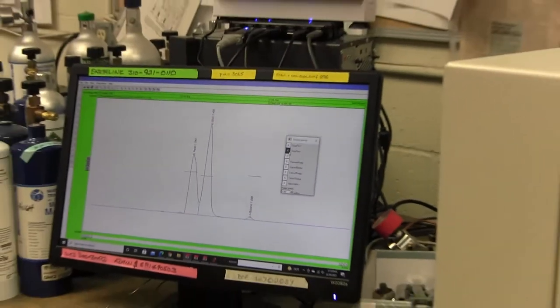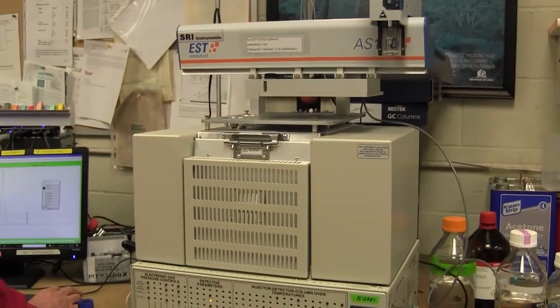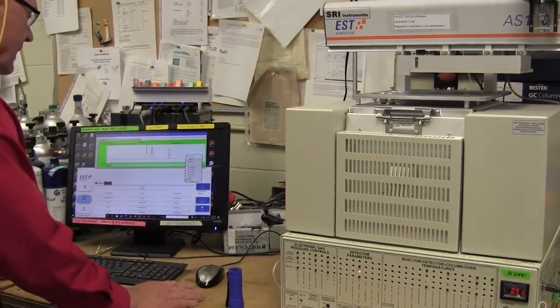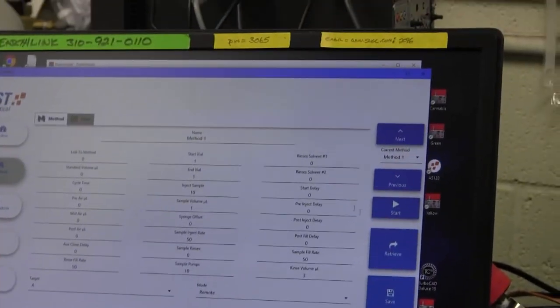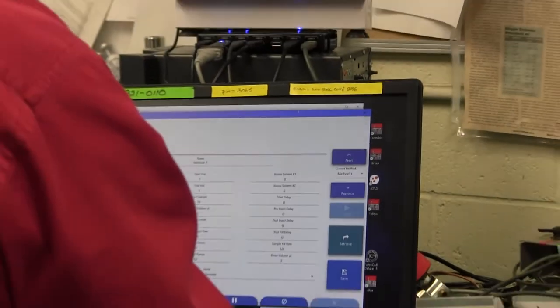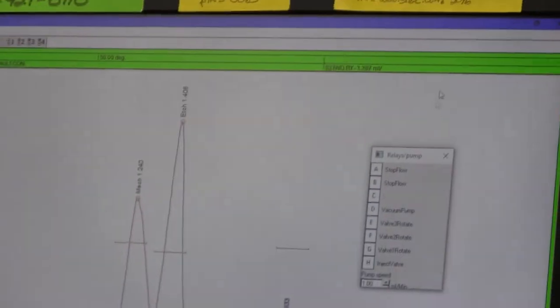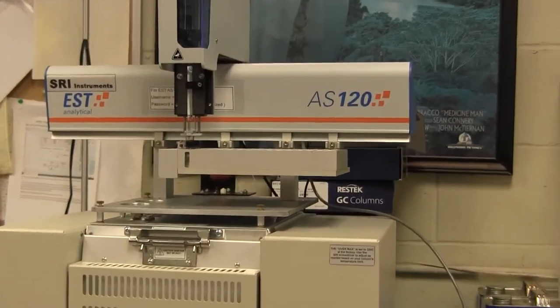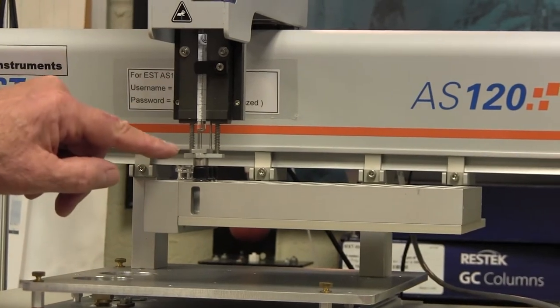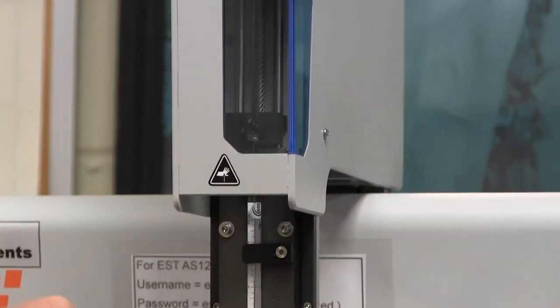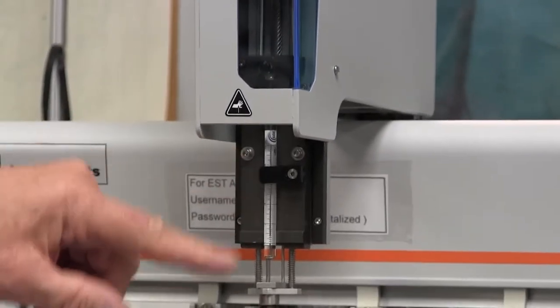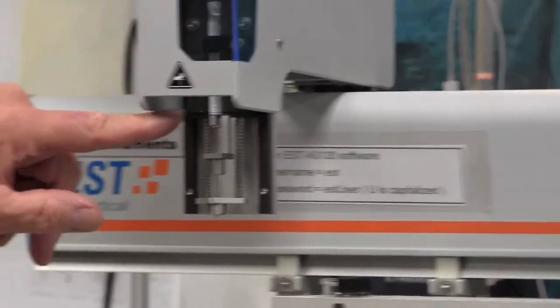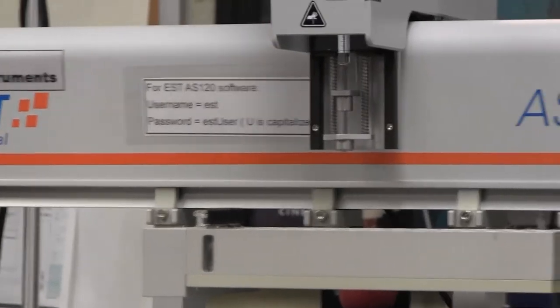So we've designed the system so that you can basically tell the system go, do your sequence by clicking this relay B and leaving it on. So I'm going to do that and watch what happens with the auto sampler. So I'm going to click relay B. I guess because I made a mistake, I forgot to hit start. So that's good that you saw me make that mistake. So first I have to hit the start button. So the auto sampler says okay, I'm ready to go. And then in PeakSimple, I click relay B and lo and behold, auto sampler goes and does its sequence just like I told it. So right now it's gone to vial number one and you may not be able to see the plunger going up and down in this little window, but it's pumping the sample just as many times as I told it to, which was 10 times. I said pump it 10 times to get out any air bubbles and then take one microliter and go over to the injection port and squirt it in there and then go back to the home position.